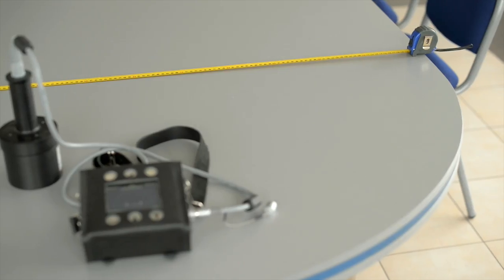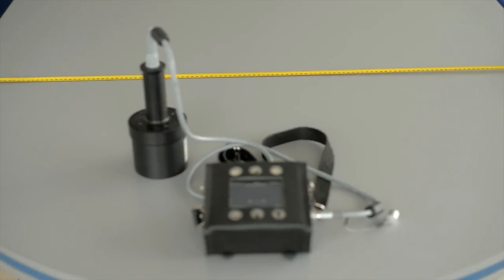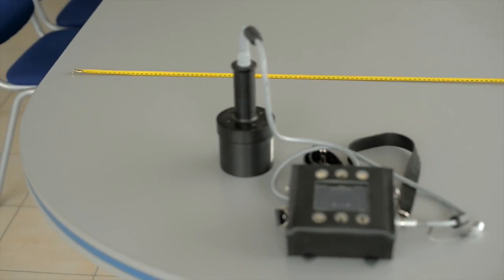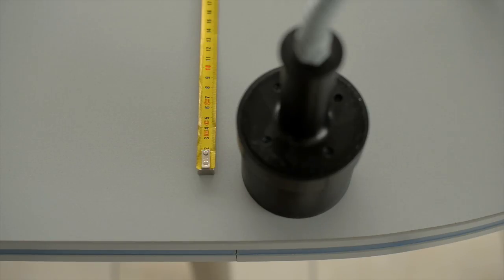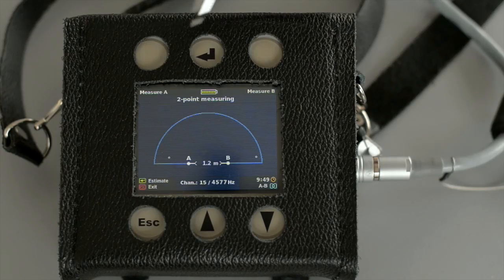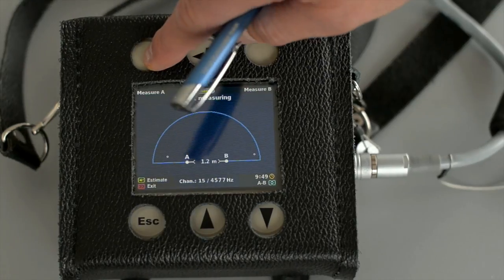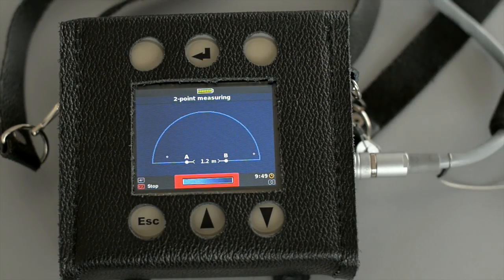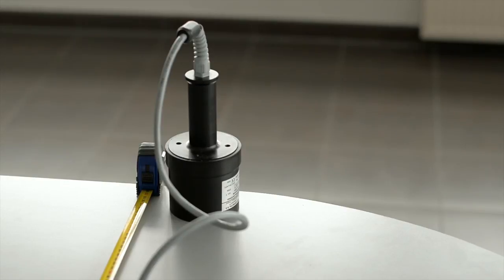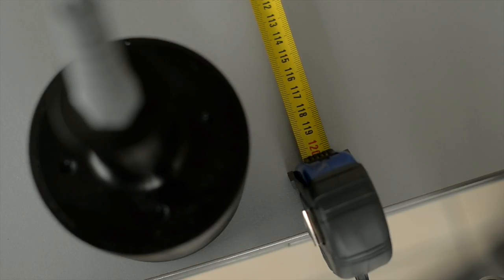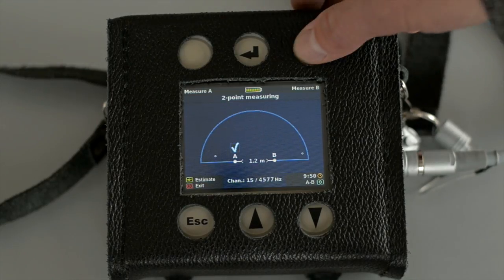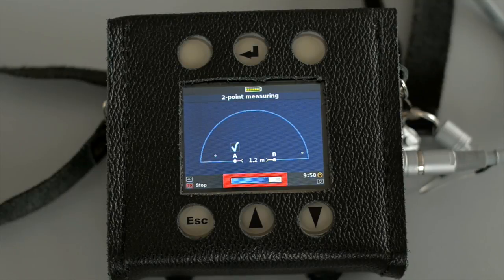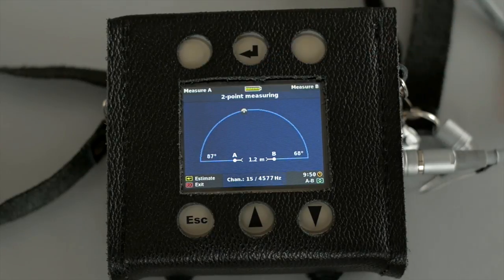In this case, it is 1,2 meters. We'll place the antenna at the two sides of the ruler, point A and point B. Point A is placed at 0 centimeters. Then we press the Measure A key and execute the measurement. Then we place the antenna at point B, that is 120 centimeters away from point A. Then we press the Measure B key and execute the measurement. When we press the Enter key, the result of the measurement is shown on the display.